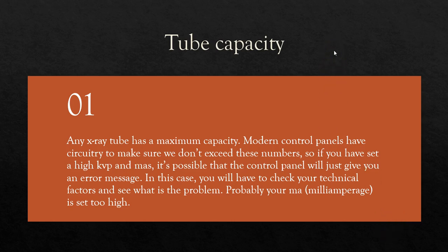The reason this is important is because of tube capacity. All x-ray tubes have a maximum capacity. And modern control panels have breaker switches — basically the computer knows how much heat and how much energy its particular tube can handle, and it's not going to let you exceed that limit. So if you dial some crazy technique, like really high KVP and really high MA, and you go to make your exposure, it's possible that the computer will stop you and give you an error message.